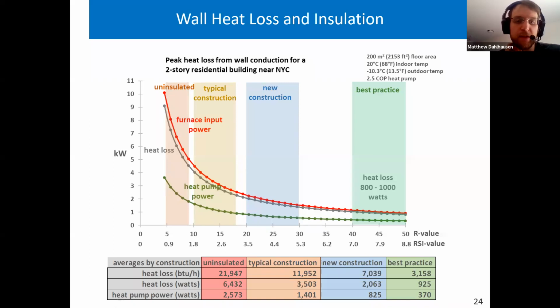Wall losses may be about 15 to 20% of the total heat loss, so a heat pump heated home may have around a 7 kilowatt peak winter demand. Scaling that up, 1,000 homes is 7 megawatts, and 1 million homes is 7 gigawatts. There are 3.5 million homes in New York, and the state electric grid currently has a 24 gigawatt winter peak. So that gives you a sense of the possible increase on the electric grid by electrifying residential building heating.